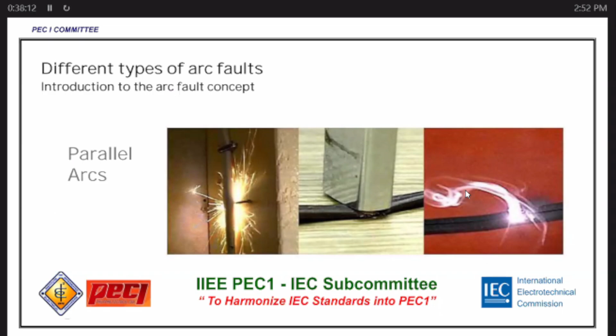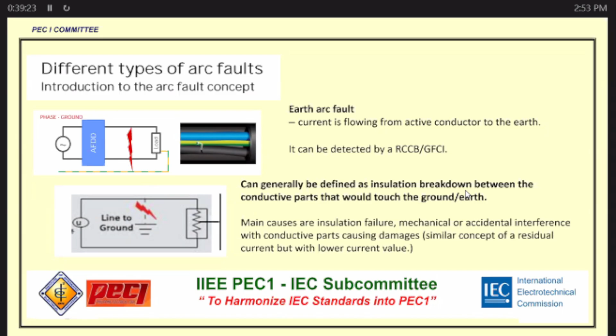The next is what we call the earth arc fault. The main causes are insulation failure, mechanical or accidental interference with a conductive part. This is what we call line to ground. Line to ground fault, where current flows from an active conductor, and it can generally be defined as an insulation breakdown between conductive parts that would touch the ground or the earth. What happens is an intermittent touching, not a continuous line to ground fault. If your protection is not a GFCI or residual circuit breaker, if it is just an ordinary molded case or miniature one, this still cannot be detected. That's why when it goes on for a long time, that's where we get fires.